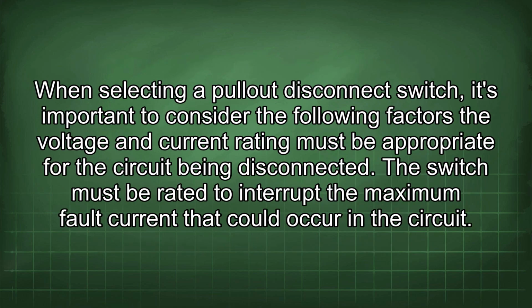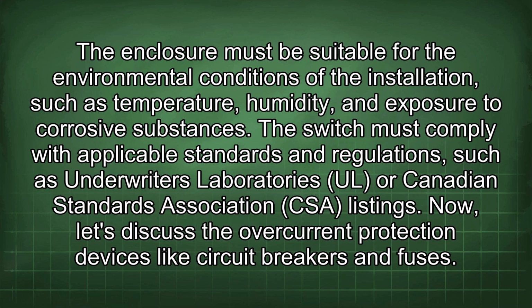When selecting a pullout disconnect switch, it's important to consider the following factors. The voltage and current rating must be appropriate for the circuit being disconnected. The switch must be rated to interrupt the maximum fault current that could occur in the circuit. The enclosure must be suitable for the environmental conditions of the installation, such as temperature, humidity, and exposure to corrosive substances. The switch must comply with applicable standards and regulations, such as Underwriters Laboratories (UL) or Canadian Standards Association (CSA) listings.